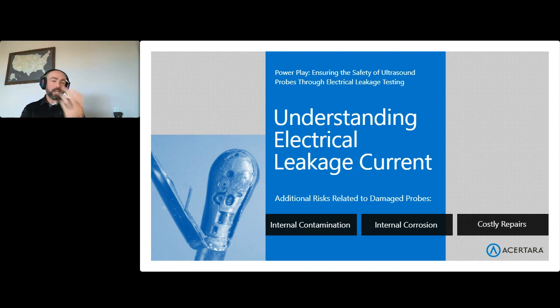Why electric leakage testing is important is that often with visual inspection, I'm sure that you guys do a great job, but electric leakage testing will find things that you don't see. You can't see the problem, that's the problem. Often you'll start to see worn insulators or holes that are going to be uncovered by disciplined electrical leakage testing that will not be evident to the naked eye necessarily. Internal contamination and internal corrosion all lead to costly repairs, or in the worst cases you have to actually replace that transducer, that probe.